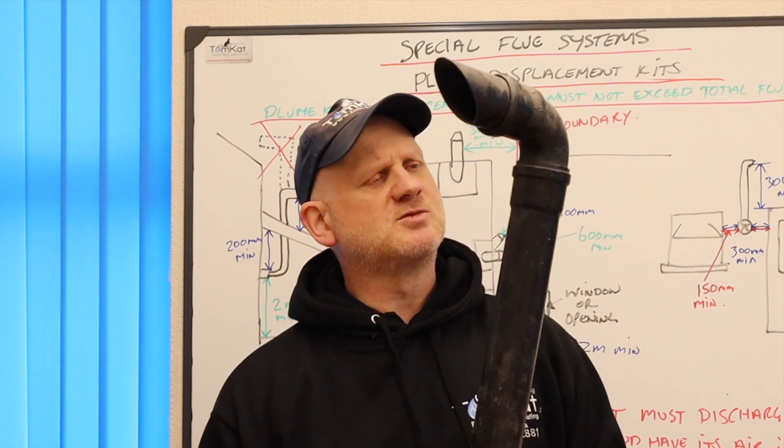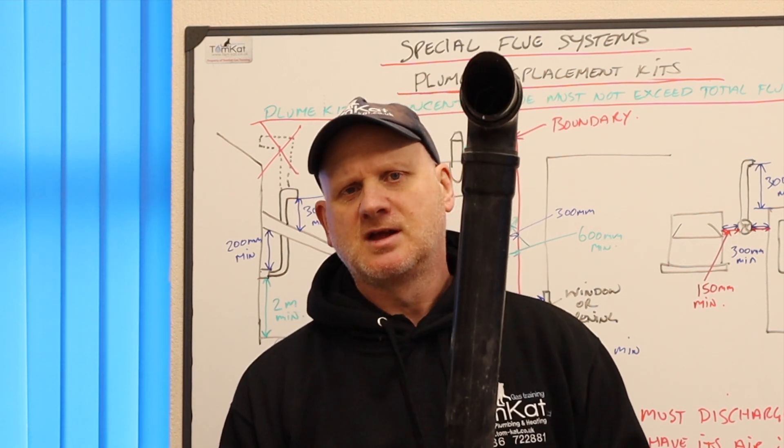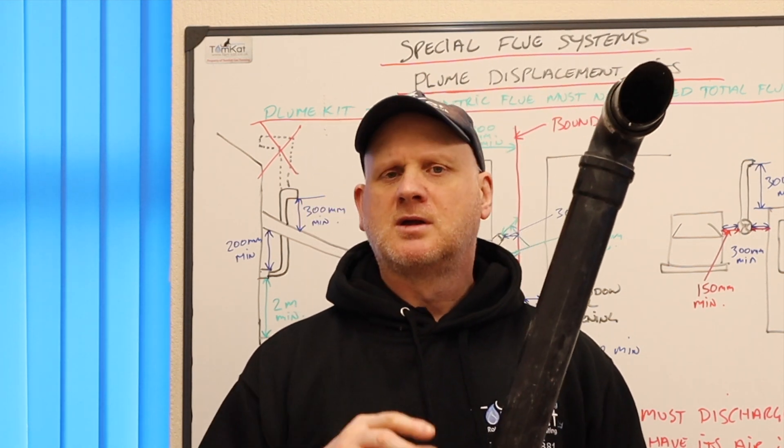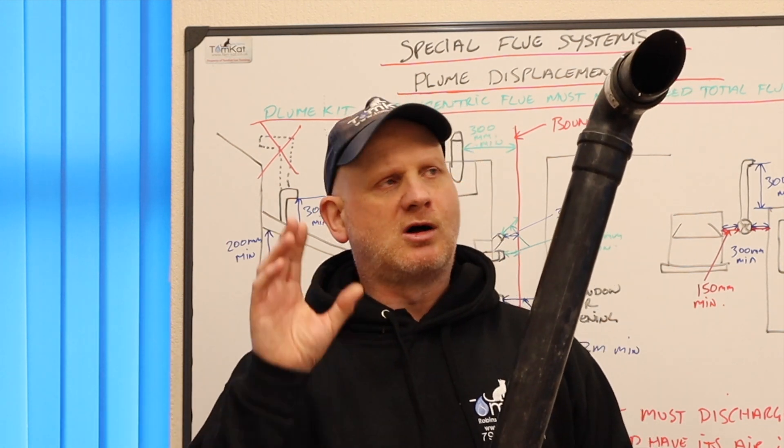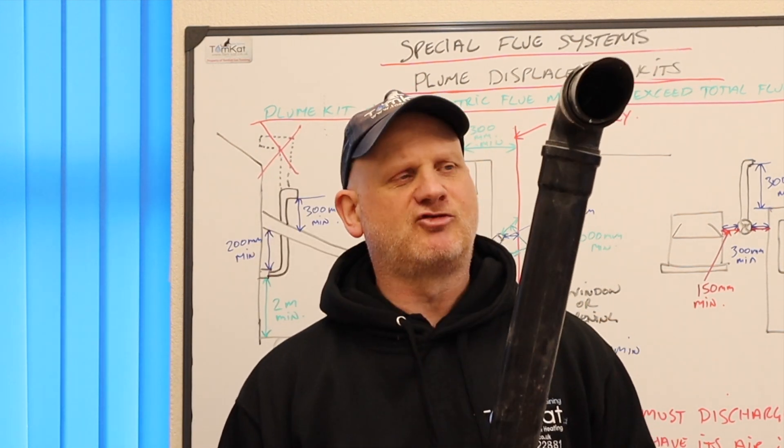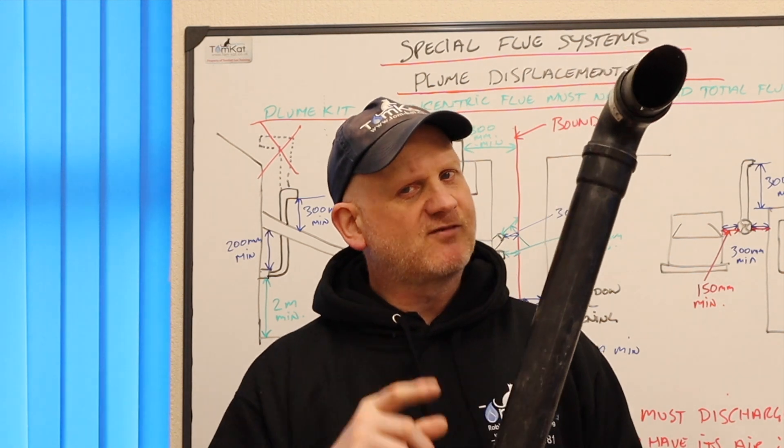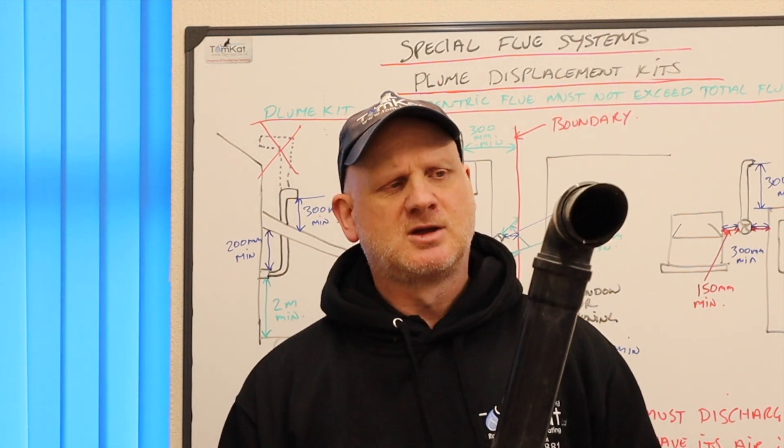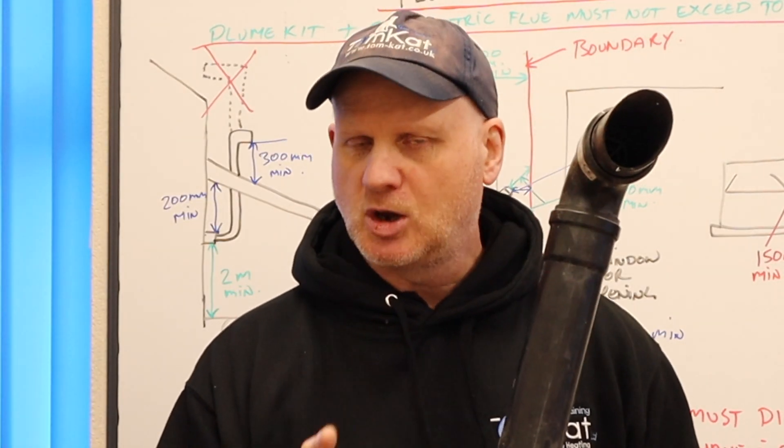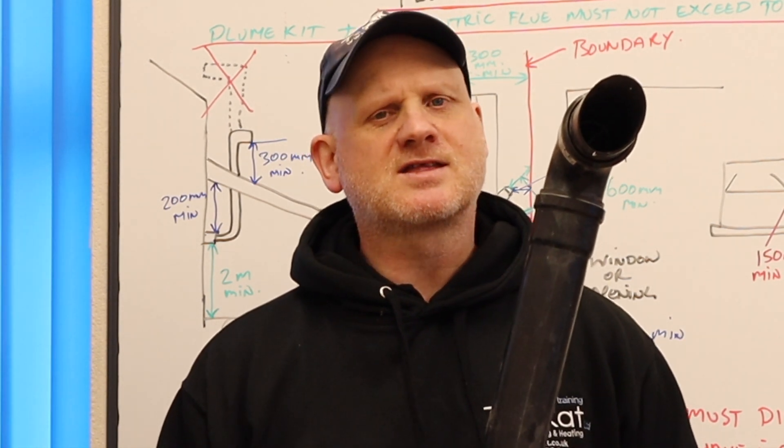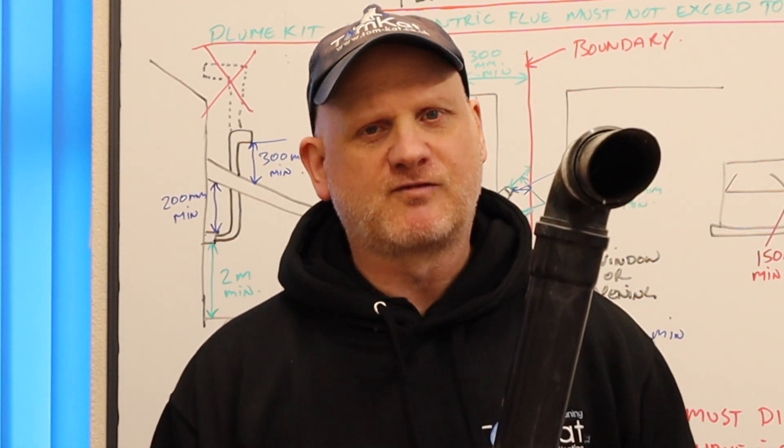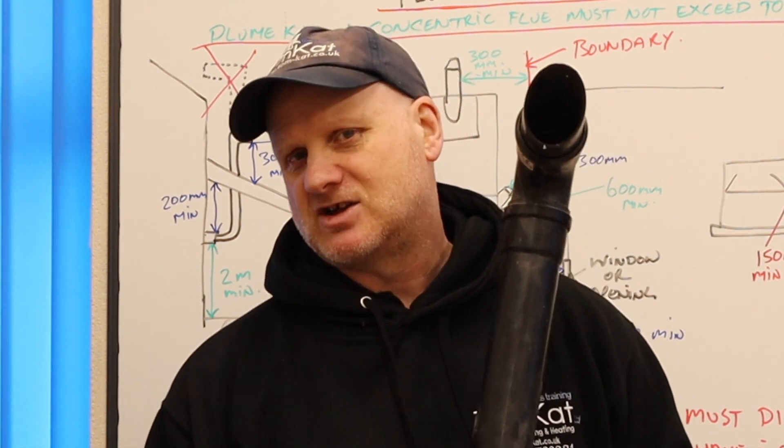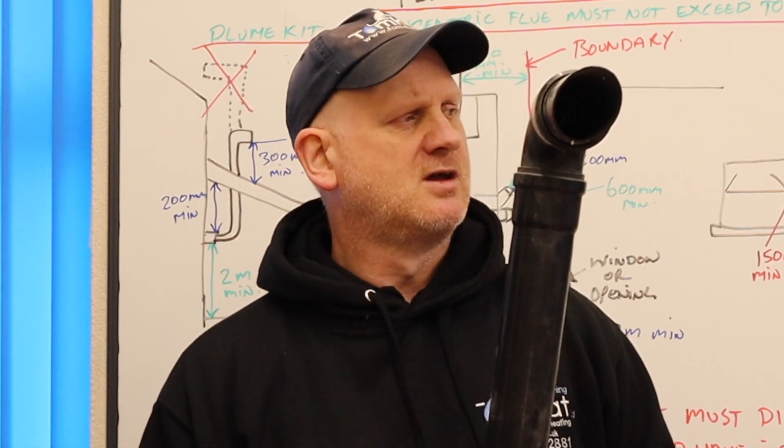And this extension piece will then be able to take us away from windows and doors or pluming onto somebody's boundary, but only if the manufacturer allows you to because we cannot use a plume kit to get us out of an illegal installation for a flue unless the manufacturers say we can do it. So let's have a look at a few of the do's and don'ts then with plume management kits.